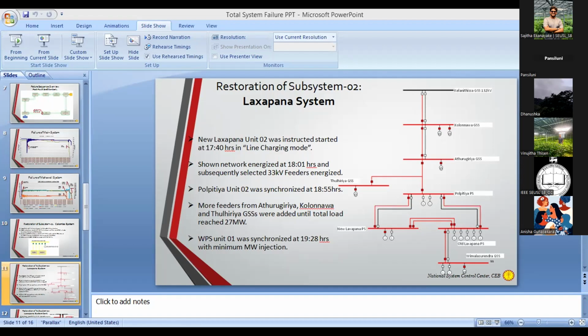The one thing is that at the moment of total failure, let's say for example, the demand was 2000 megawatts. If you just connect one machine, that single machine cannot supply that much demand. That's one reason, right? That 2000 megawatts is supplied by so many generators. Once the whole system collapses, by connecting only one machine you can't supply that demand. Then definitely the first machine you connect into the system will be tripped.